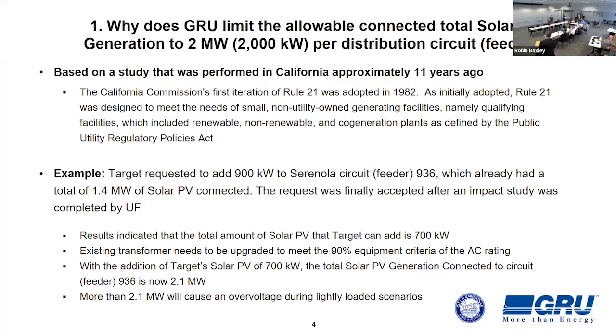In this case, we partnered with the University of Florida Electrical Engineering Department, and their team did a study on this distribution feeder, Serenola 936. They determined that 900 kW would cause an overvoltage exceeding the limits set by the Public Service Commission under lightly loading conditions, but 700 kW could be connected without causing any voltage issues. So we went back to Target and told them 700 kW was the maximum they could connect.